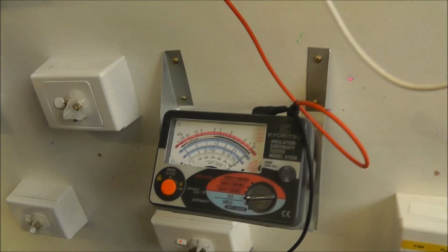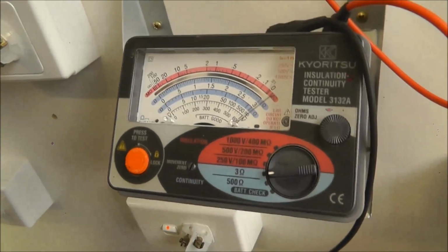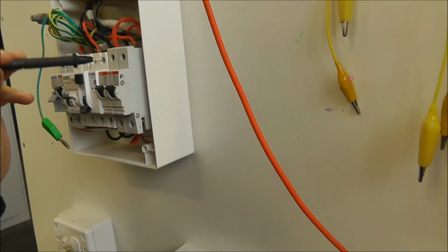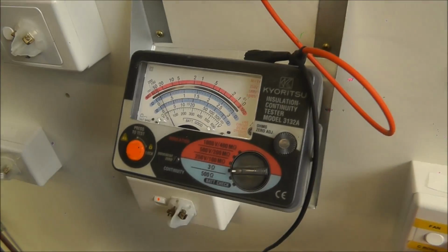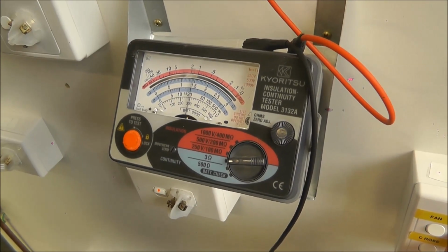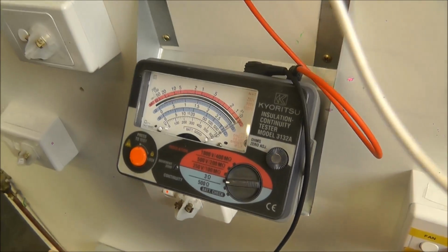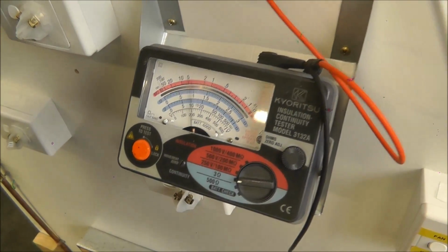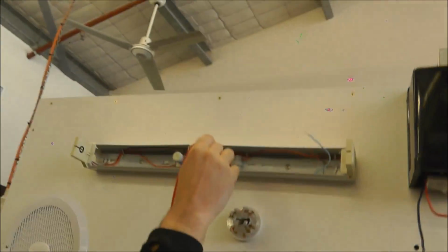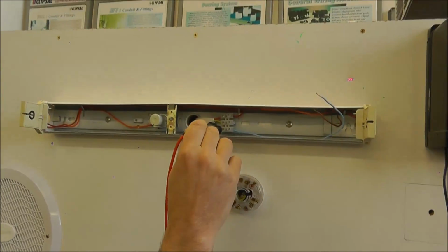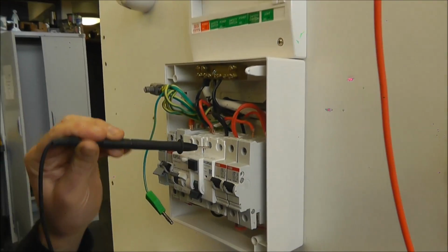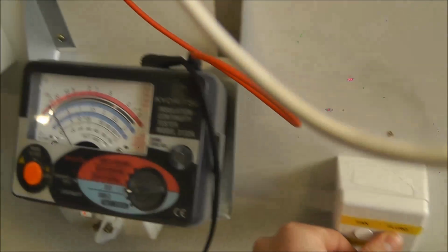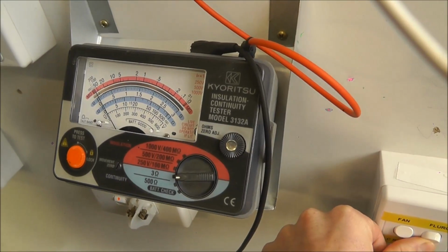Okay, over here I'll check the fluoro between active, I'll just turn this back on again, active and active. Hit the fluoro switch, Dobbo. It's taken the RCD out, so I'll go back over here, it's on that one. Is the fluoro switched? Now that's the active. Now let's just check, so that's fine. What would I do if it was a neutral? I'd have to go to the neutral up here and go to the neutral of the final sub-circuit and flick the switch. Fluoro, yeah. Well, once you've established that one switches, it's fine.